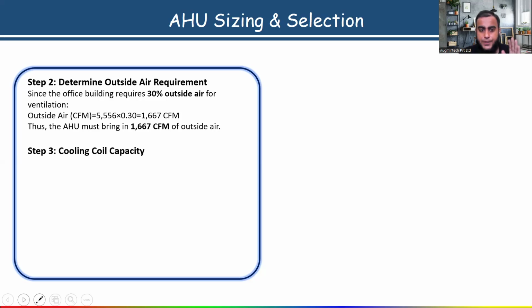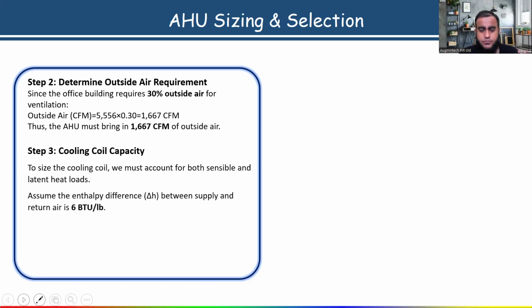Now in the third step, cooling coil capacity. The formula I am using is simple. Let's say we know the enthalpy difference, delta H, between supply and return is 6 BTU per pound. If you know the enthalpy and airflow, the formula is 4.5 into airflow value into delta H. Here we are assuming delta H of 6. As per that, see how much cooling capacity we have got: 1,49,022 BTU per hour. This is our cooling capacity.